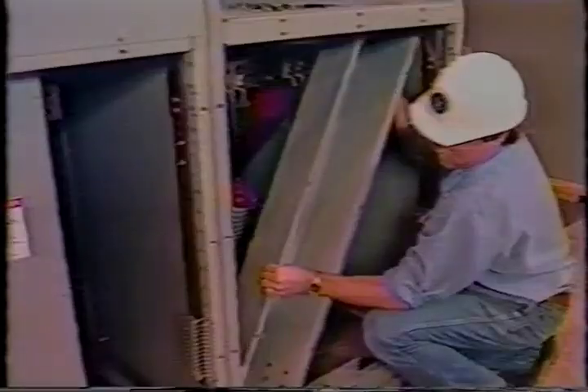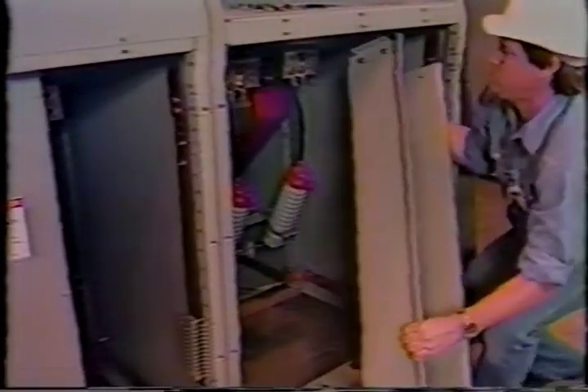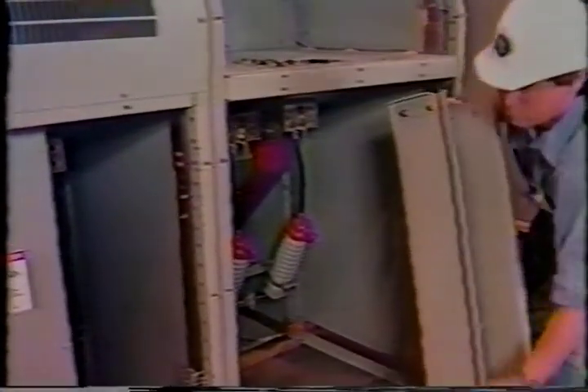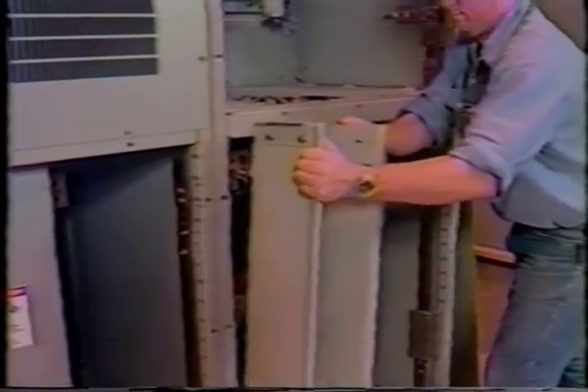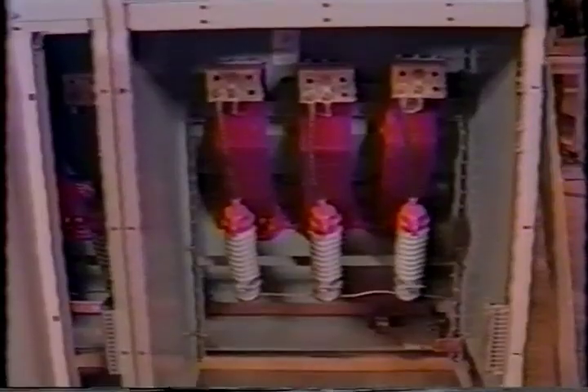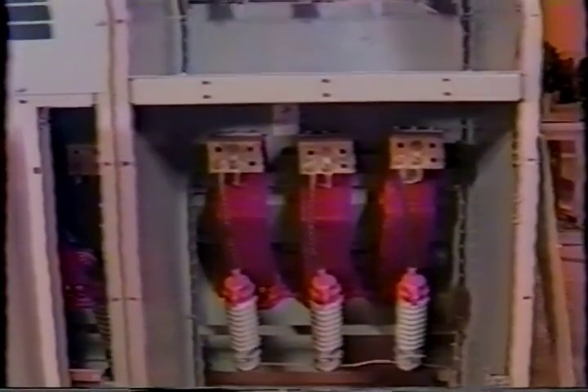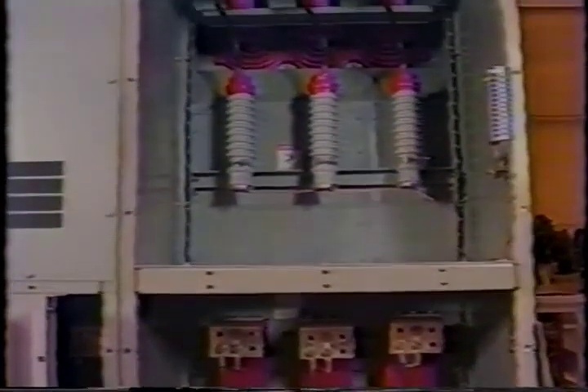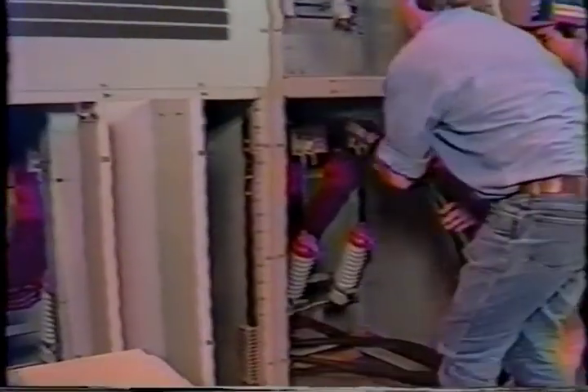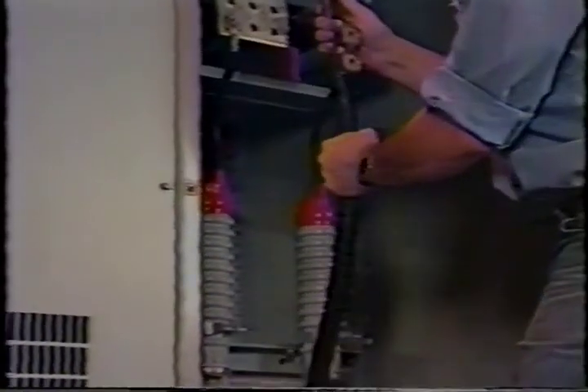If two systems are to be paralleled, be sure the phase rotation and phase angle are the same to prevent damaging equipment. The rotation must conform to the shop order drawings so that instruments, relays, and meters will operate properly. Follow the instructions of the cable manufacturer to determine what minimum bending radius is permitted.